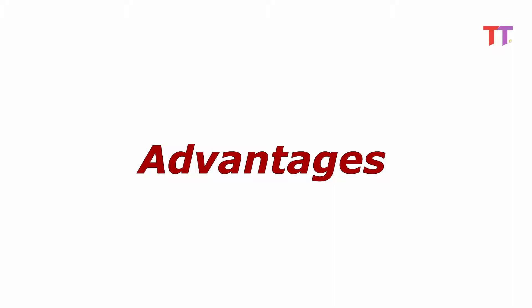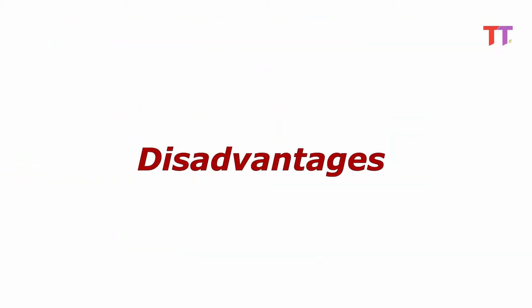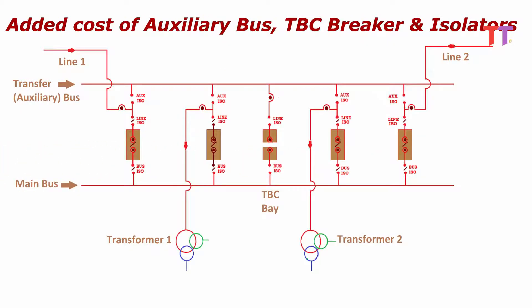Advantages of the main and transfer bus bar system: circuit breaker maintenance of any bay can be done without interrupting power supply, and this arrangement provides more flexibility. Disadvantage: the only disadvantage is that it adds up the cost of the auxiliary bus, TBC breaker, and isolators.